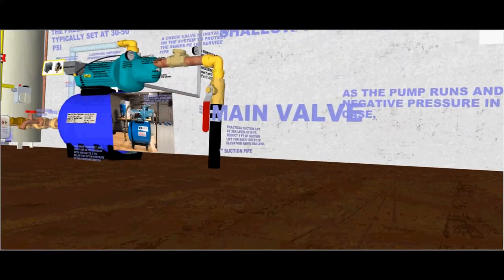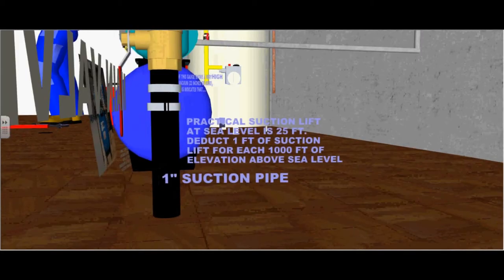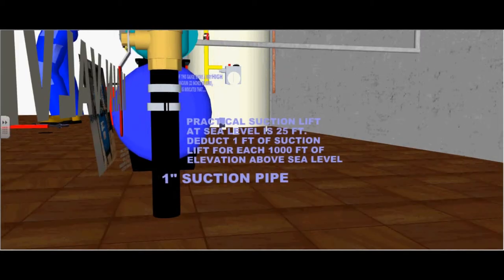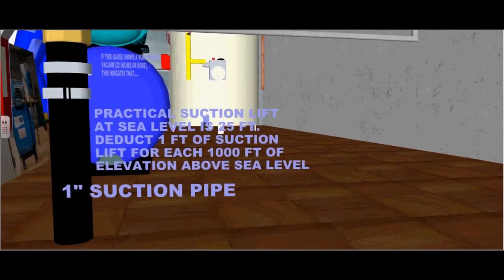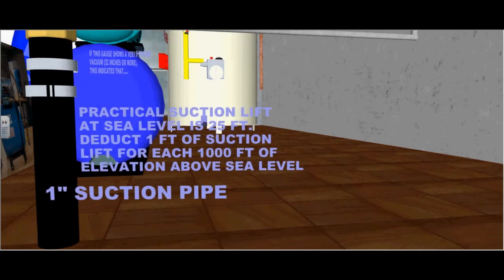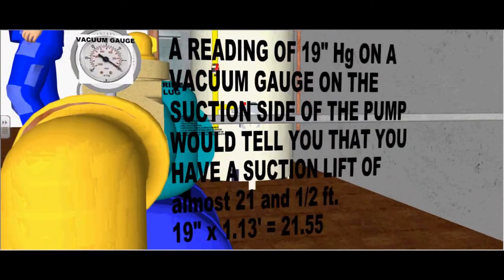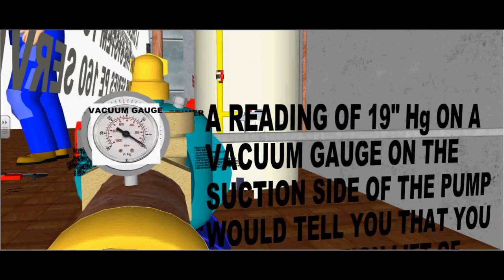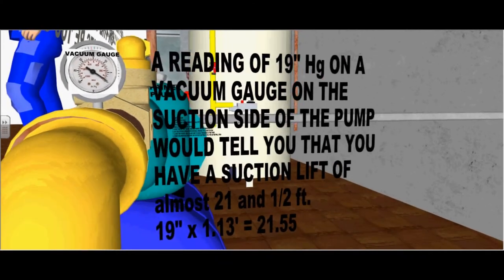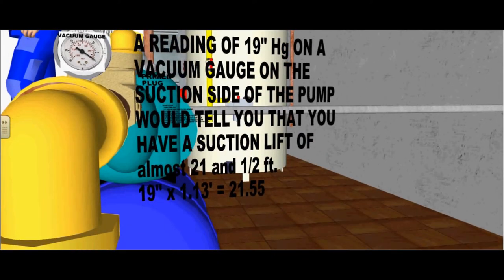This is the 1 inch suction pipe. Practical suction lift at sea level is 25 feet. Deduct 1 foot of suction lift for every 1000 feet of elevation above sea level. A reading of 19 inches mercury on the vacuum gauge on the suction side of the pump will tell you that you have a suction lift of almost 21.5 feet. 19 inches times 1.13 feet equals 21.55 feet.